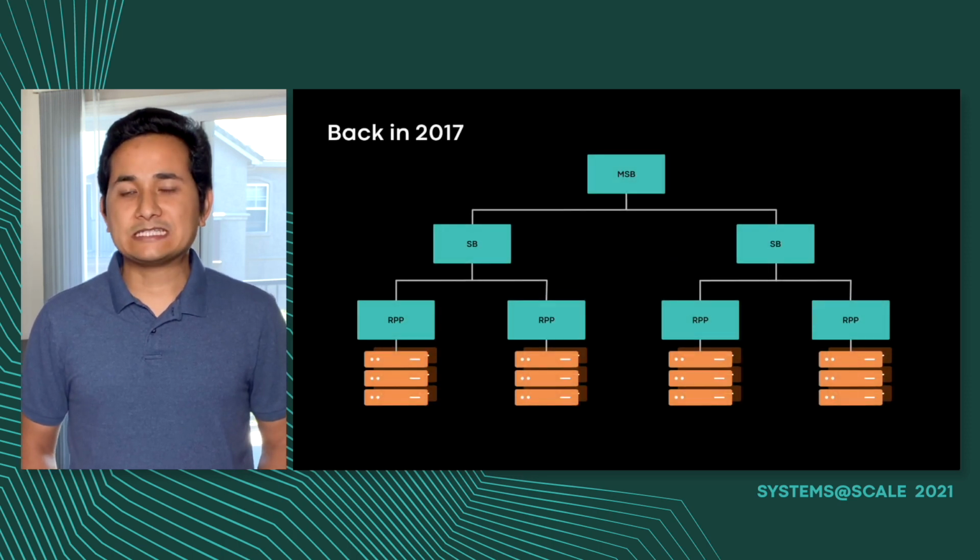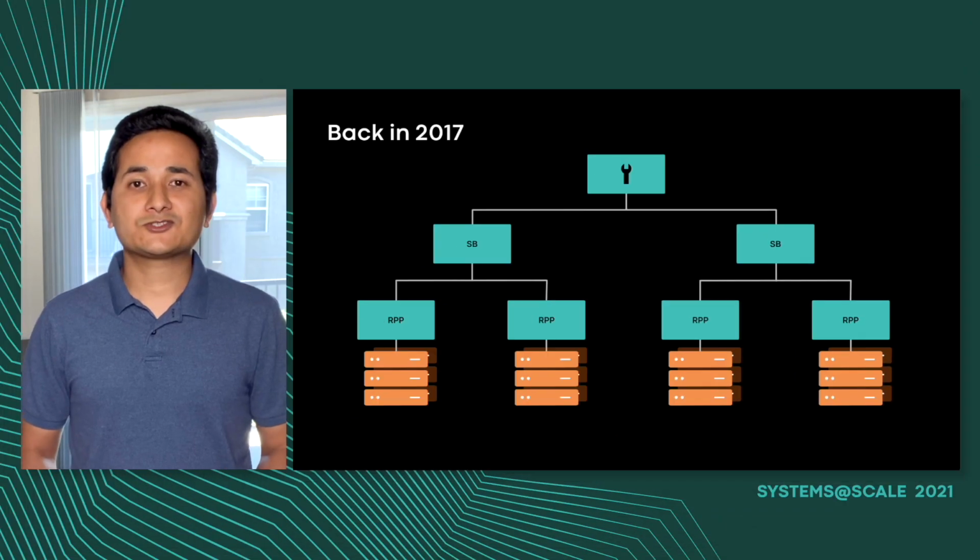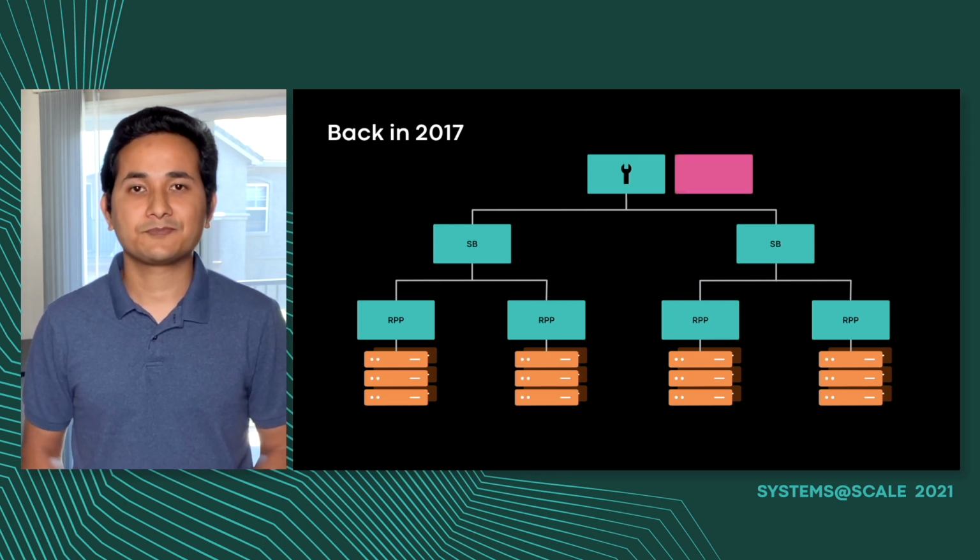Back in 2017, in Facebook's North Carolina data center, we were performing a maintenance on an MSB that didn't go as planned and led to server power outage. Let me describe how generally MSB level maintenance should have worked. Whenever we need to perform maintenance on a MSB, it needs to be isolated and de-energized. We have a reserve MSB for such purposes.